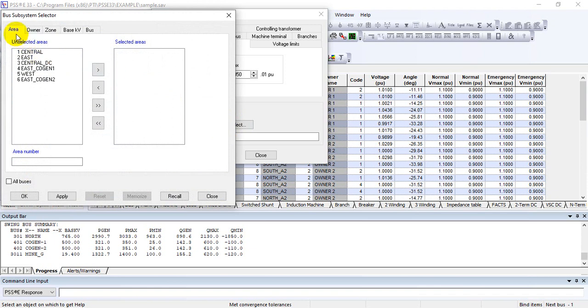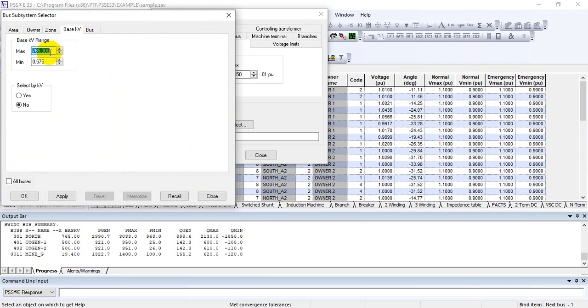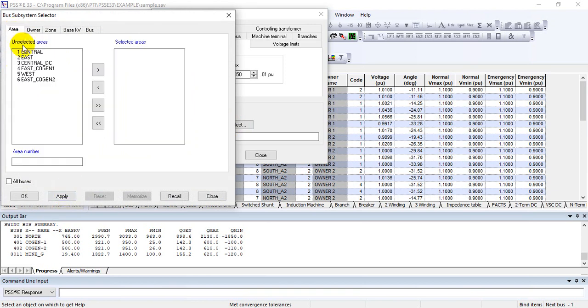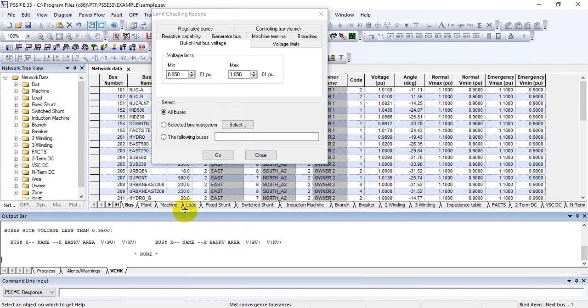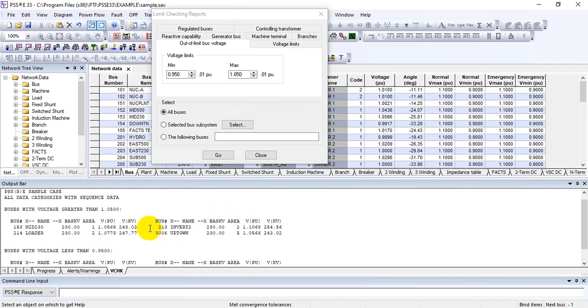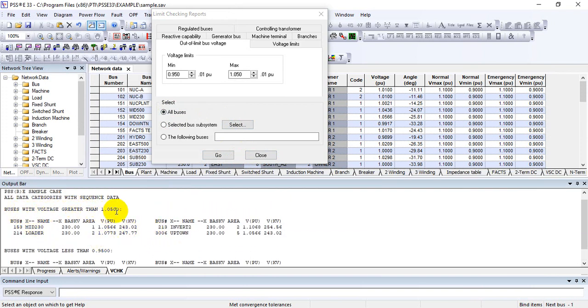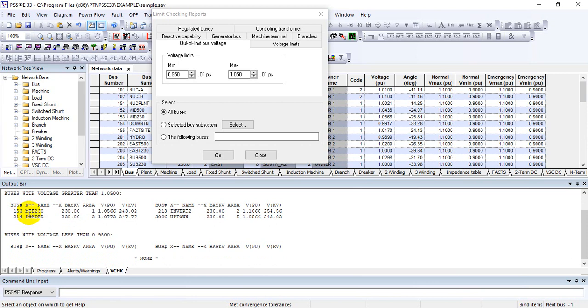You can select whatever buses you are interested in — by area, owner, zone, or base kV. For example, if you are interested in violations at 500 kV or 765 kV voltage levels you can filter by those. Select the area section and press Apply. Then select all buses and press Go. In the progress report, the Limit Checking Report appears. Buses with voltage greater than 1.05 are shown — there are four buses whose voltages are greater than 1.05, meaning these buses are violating the limits under steady state. There are no buses with voltage less than 0.95.